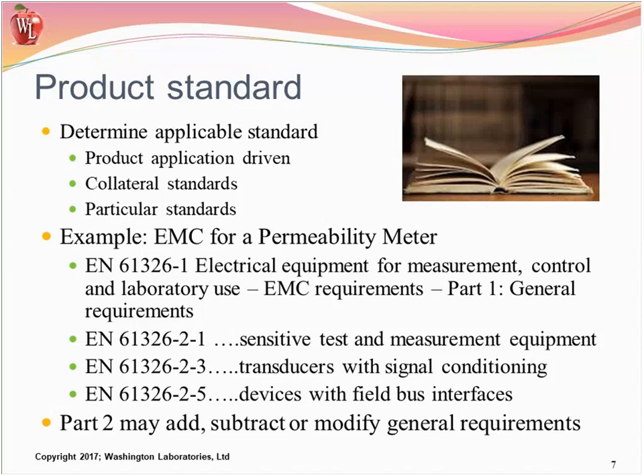So Part 1 and Part 2 are always used in conjunction, and by the way, Part 2 is dominant. If a Part 2 did not get updated when Part 1 did, then your older Part 1 may still apply, so you don't have conflicting information. Most of the time we try to evaluate to cover both areas so we stay current on everything, but sometimes the modification standard takes precedence—so the -2 standard takes precedence over the -1 if the requirements conflict.